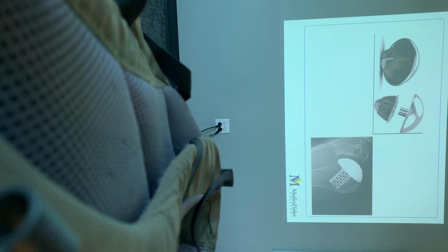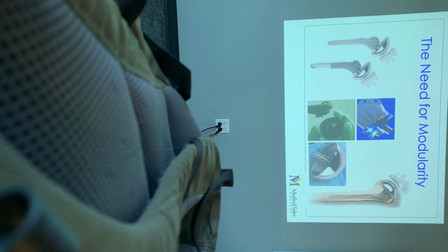So you're replacing the glenoid as well as replacing the head of the humerus, but not relying on some of the metaphysis and the diaphysis of the humerus to stabilize the implant. These are becoming quite popular, right? The stemless ones. And of course, unlike hips and unlike knees, modularity is important in the shoulder.